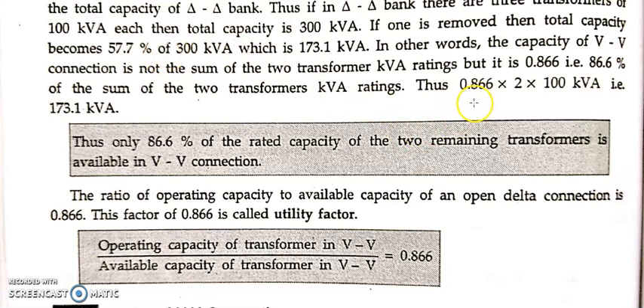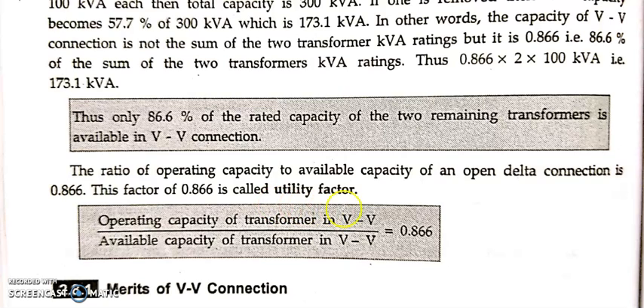The second method is what? It is 86.6% of the available transformers in service. So how many transformers are in service now? After removing one transformer out of 3, there will be 2 transformers available. So 2 transformers in the sense of 200 kVA. So 200 kVA into 86.6% will again result in the same as earlier, that is 173.1 kVA. Let us see the utility factor now.